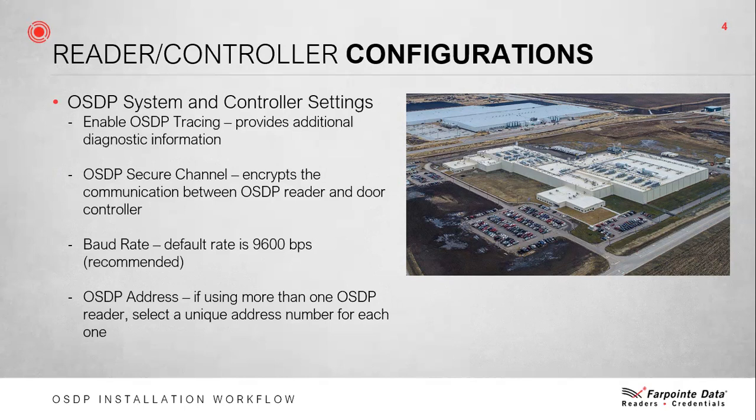OSDP secure channel is something that end users with very strict IT compliance will find very interesting, and it's information you should arm your sales team with when upgrading customers or presenting new offerings. Baud rate: the default rate is 9,600 baud and this is recommended, but the baud rate for communication between multiple readers on an RS-485 drop can be regulated. Finally, OSDP addressing: if you are utilizing multi-drop topology with more than one device per port, a unique address must be assigned to each device. This address is assigned by the controller and facilitated by the reader.